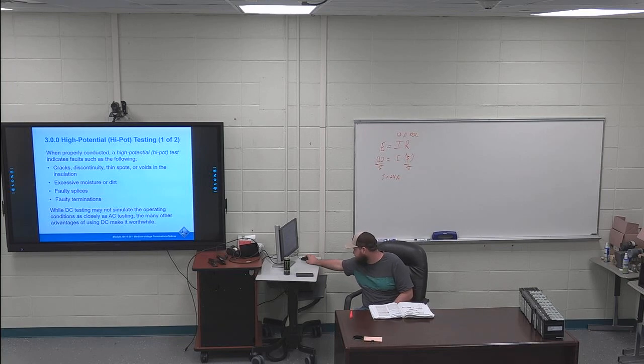just this sentence that's on the board at the bottom is the one I have highlighted, all the way in the bottom left of page 29. Although DC testing may not simulate the operating conditions as closely as AC testing, the many other advantages of using DC make it worthwhile. So DC is mostly used, but you need to know that AC testing resembles the operating characteristics most closely. So using AC is the closest to testing stuff in normal operation.